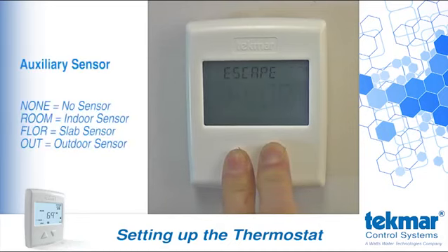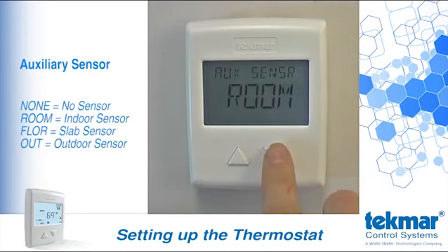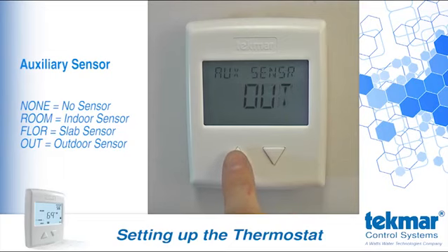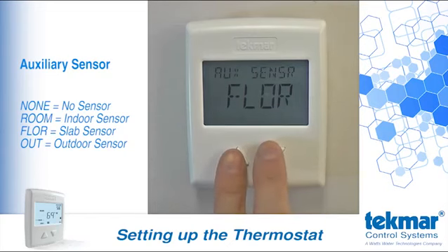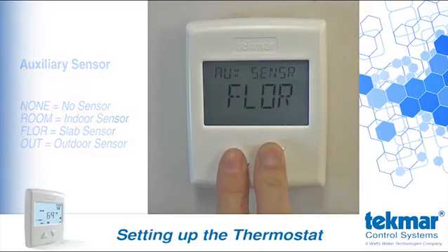The first setting here specifies the auxiliary sensor. Are you using a floor sensor, a remote room sensor, or an outdoor sensor? Remember, since this thermostat will detect the presence of an auxiliary sensor, this setting will only appear if you are indeed using an auxiliary sensor.